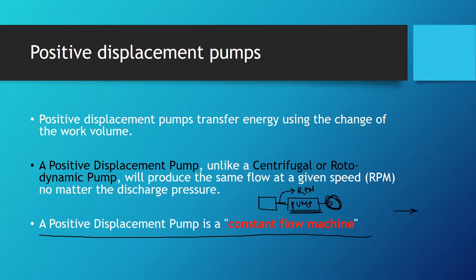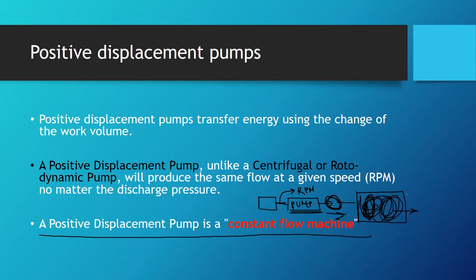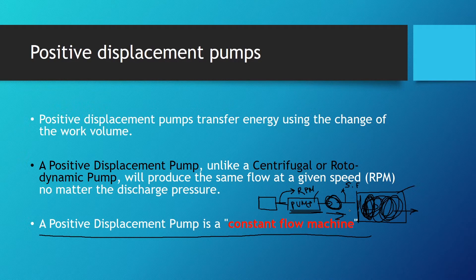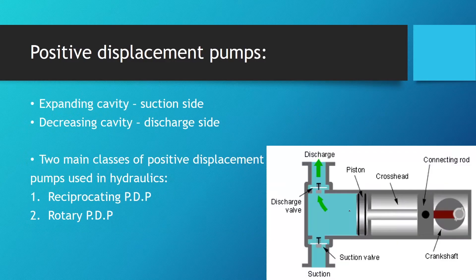If a pump is connected to a tank, it's just going to generate flow until the pressure rises and the tank bursts or the pump malfunctions. That's why we always need a safety valve after a positive displacement pump, as shown in the picture.